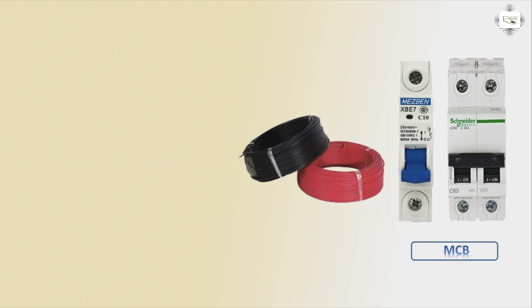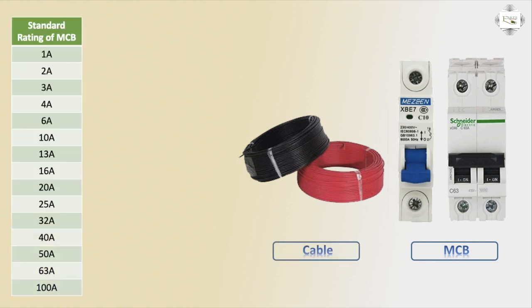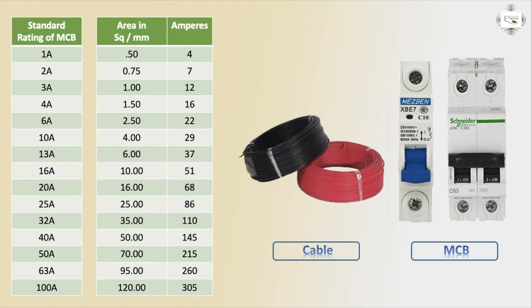The standard rating of MCB for electric wire and cable are: 1, 2, 3, 4, 6, 10, 16, 20, 25, 32, 40, 50, 63, and 100 amperes. Based on our calculation, we select the standard 10 ampere circuit breaker.